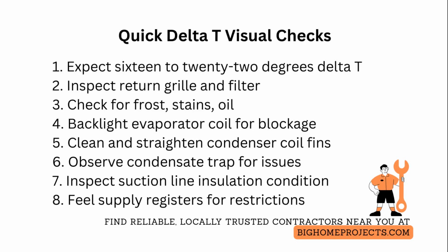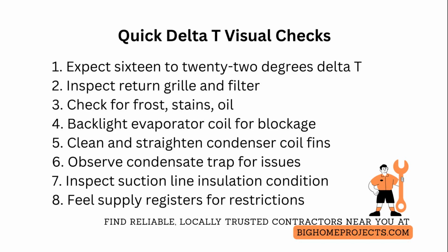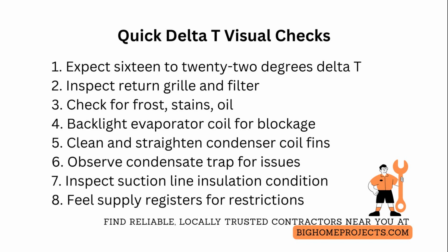Shine a light through the evaporator coil fins. If light does not pass evenly, you have impacted dust or biological growth. Note any matting near the bottom 2 inches where condensate carries debris.